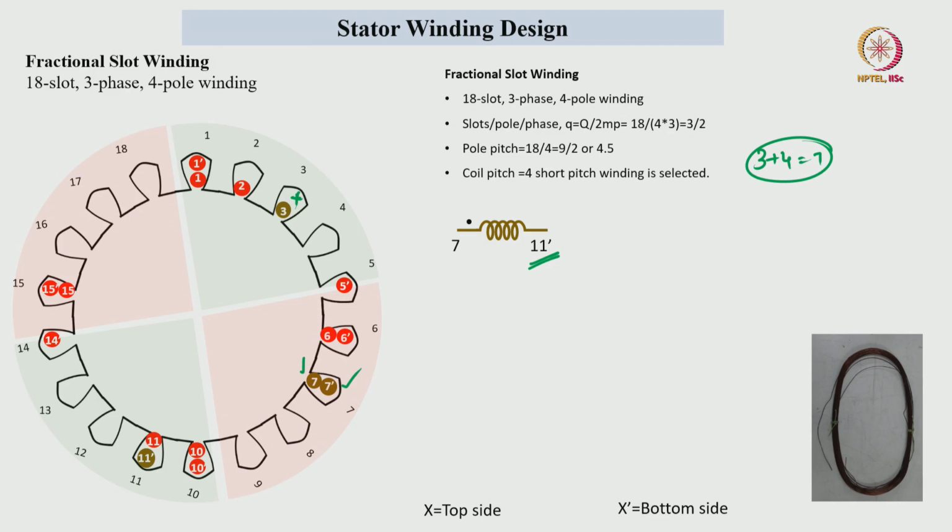Otherwise, the conductors related to the B phase would be completely placed in the third slot and 7th slot, both coming in the forward direction. If we do it in that manner, the winding symmetry will not come with respect to the end ring. For that reason, leave the coils which have to be placed in the second slot and third slot bottom side. At the end we will fill these two positions. Now, we will go in the forward direction.